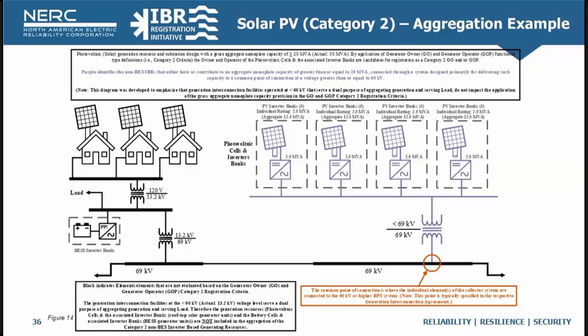The example Pete gave, shown on the screen here—you couldn't look at this diagram and say the purple facilities are serving the load of those houses downstream on the 69 kV line. That wouldn't be appropriate, because this purple system has a common interconnection point with a system designed for delivering capacity to that point. What happens beyond that point is a separate matter. Even if there's generation connected down there on the distribution system, that's evaluated separately and can't be subtracted out from this battery or solar system shown here. So hopefully that answers the question.